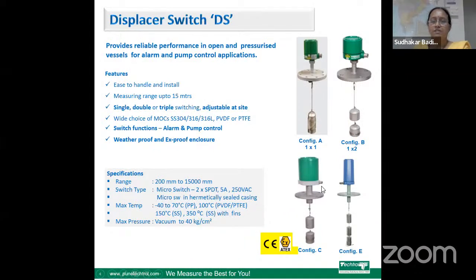Now this is a displacer switch. It gives reliable performance in open and pressurized tanks and is generally used for alarm and pump control applications. The features are, it is very easy to install and handle also. The maximum range is available up to 15 meters. You will get single, double and triple switching points, and these switching points can be adjustable at site.